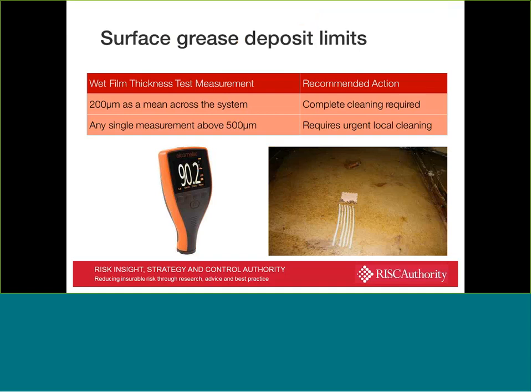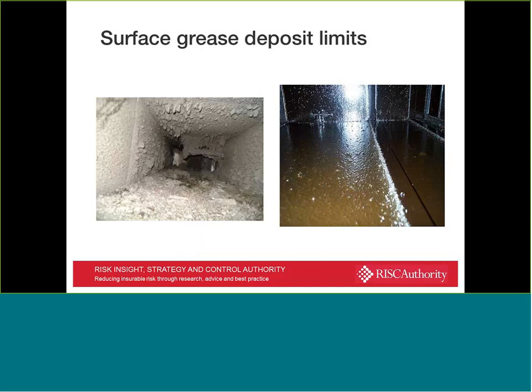These are very much rules of thumb, and if you're working with a system or an organisation with systems that are monitoring the deposits on a regular basis, then it's certainly something that can be applied. However, you'd like to think that in real terms, over time, a risk-assessed approach to the frequency of internal cleaning has come up with a frequency that is ensuring that those levels aren't met at any point, and that cleaning is undertaken before those particular levels, or depths, of grease are actually achieved.